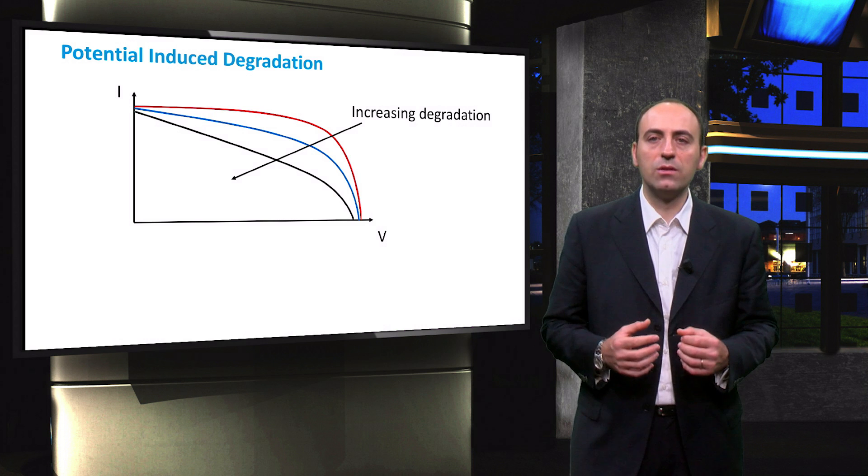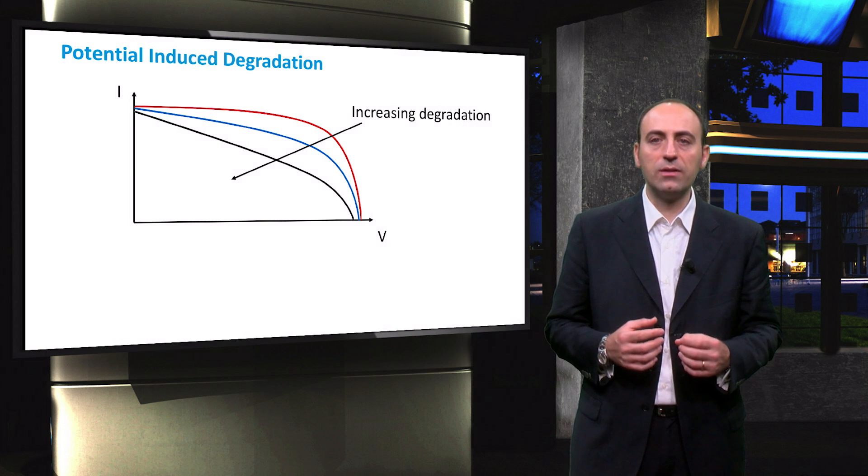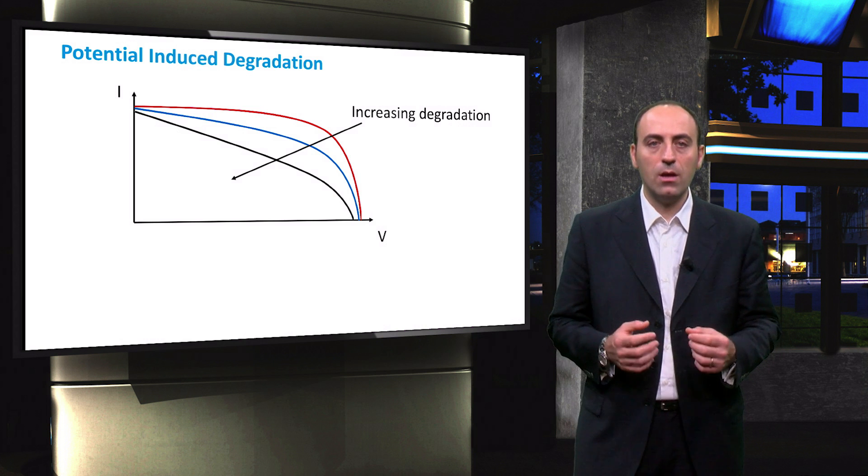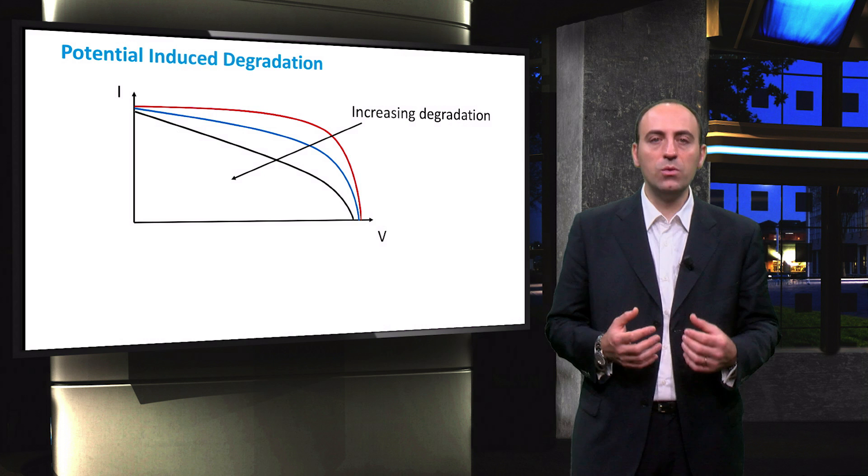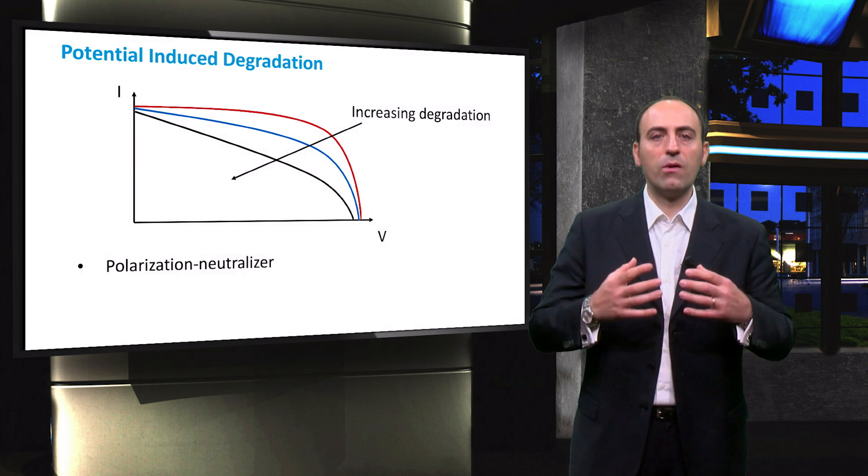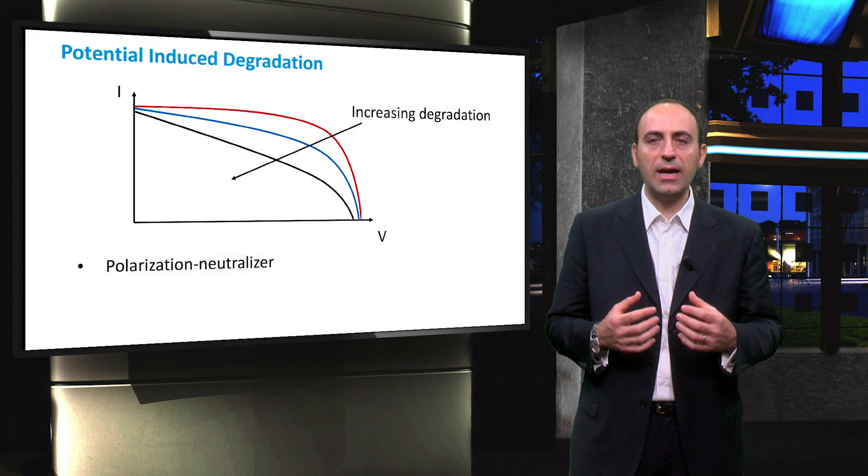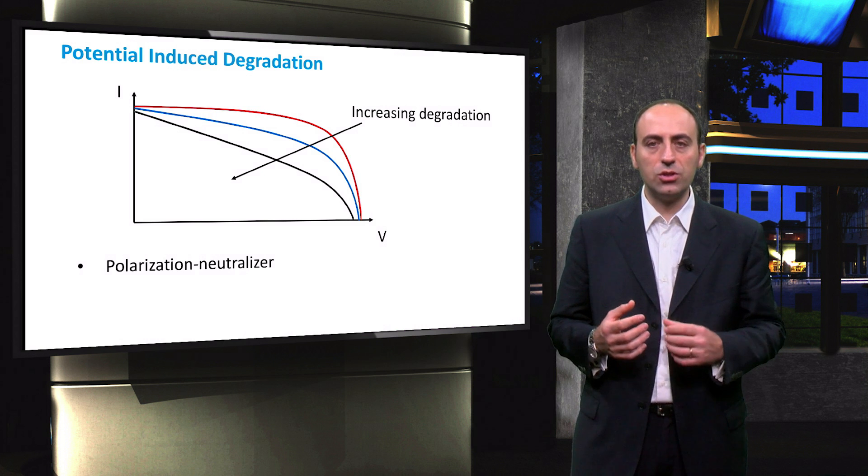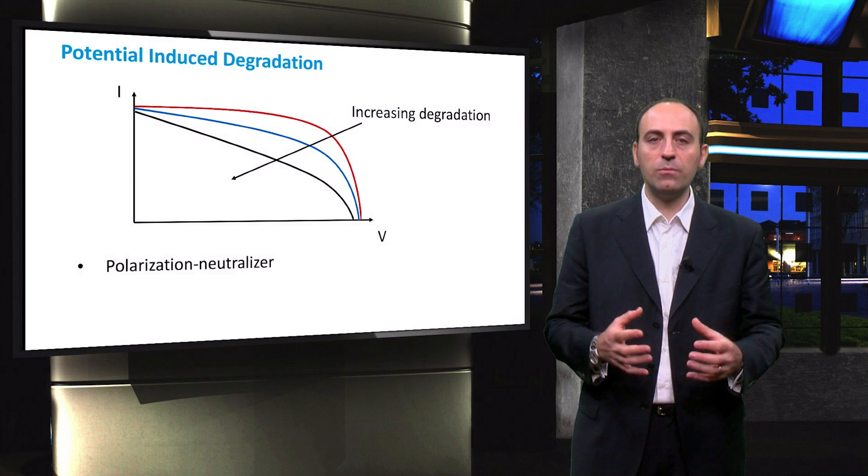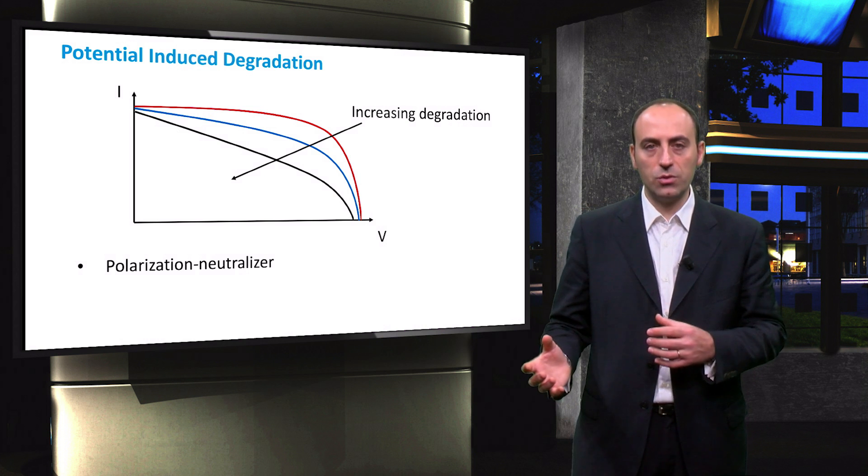The open circuit voltage and the short circuit current remain nearly unchanged, but the maximum power point can be reduced up to 70%. There are different ways of reducing the PID. One method is to use a polarization neutralizer that applies a reverse voltage to the affected pole overnight. This solution is preferred when the array cannot be grounded because of the inverter chosen.